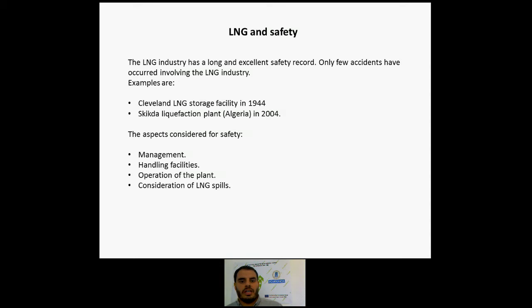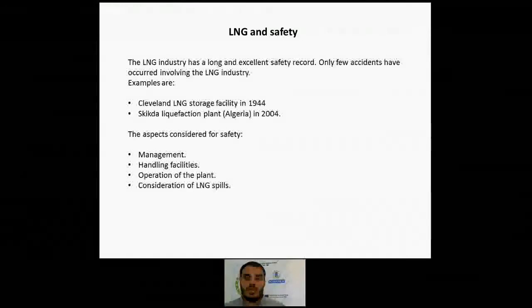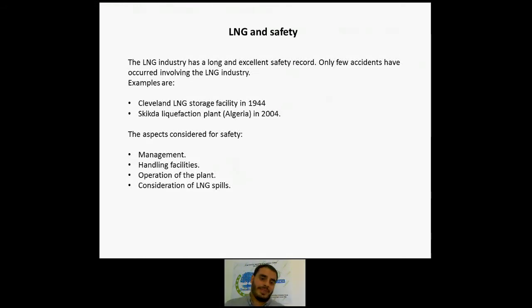The explosion, along with the shrapnel from the ruptured steam drum, caused further damage to the process piping and pressure vessels in the immediate area, leading to additional flammable fluid release. The fire took 8 hours to extinguish, which is quite a lot. But the explosions and fire destroyed a portion of the LNG plant and caused 27 deaths and injured 72 more. No one outside the plant was injured, nor were the LNG storage tanks damaged by the hydrocarbon explosions.